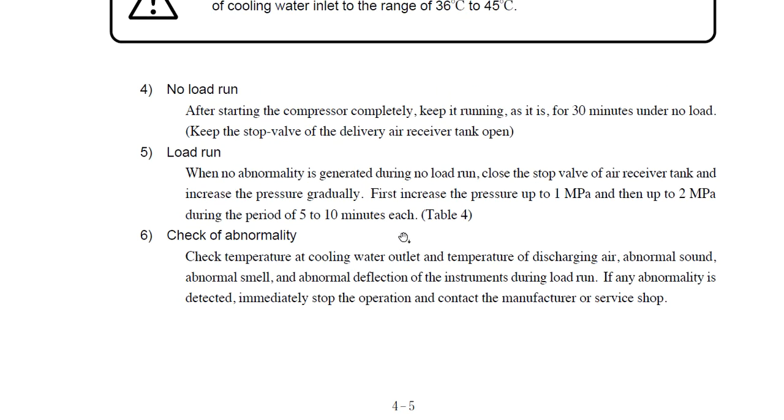Next, we will check for any abnormality, and these checks will be applied for other equipment as well. Check the temperature at the cooling water outlet and temperature of discharging air. You have always thermometers available there. We have pressure gauges available.